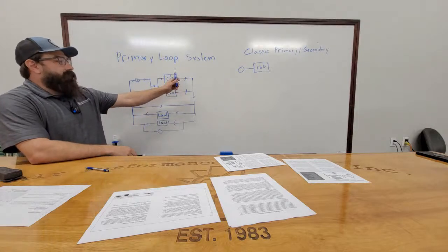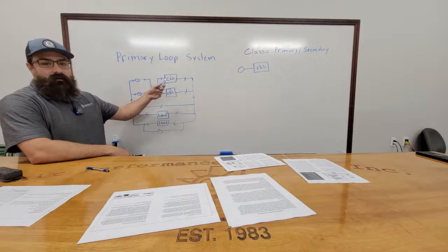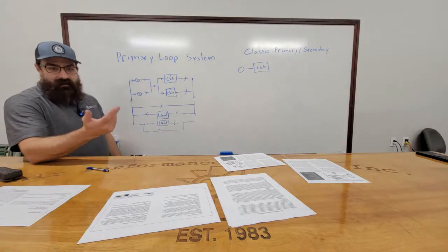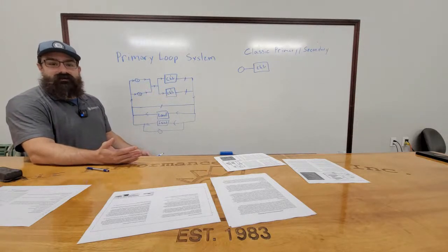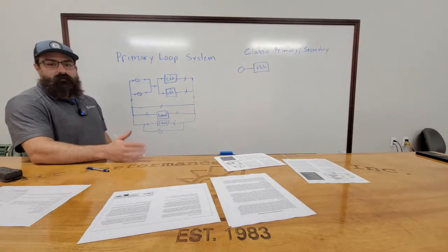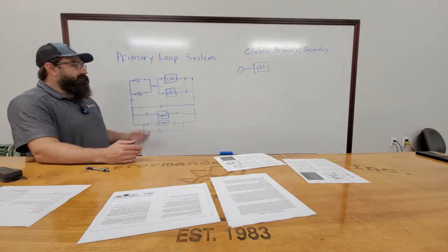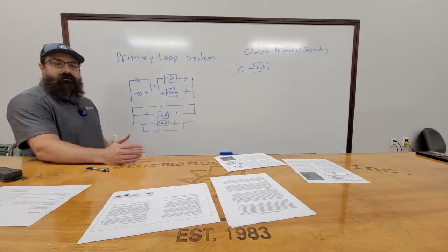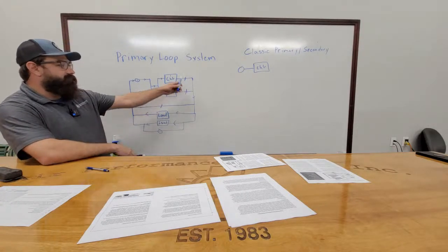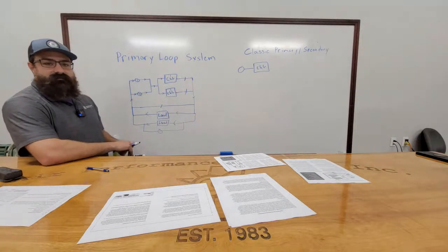But these are important. If this valve is open and this chiller is not running, you will migrate oil out of that evaporator system. And you add a false load to the system by circulating water through that coil because it's still a heat exchange no matter what. Even if it's a minimal one, you're adding a load. But the biggest thing is the migration of oil because you can starve a unit for oil and burn a compressor up. So always look for these. They can be detrimental to a system.